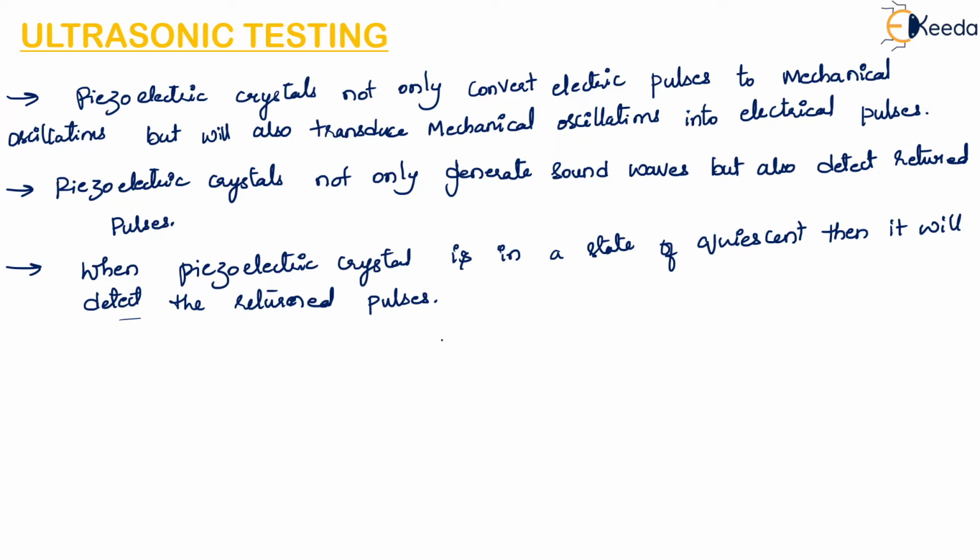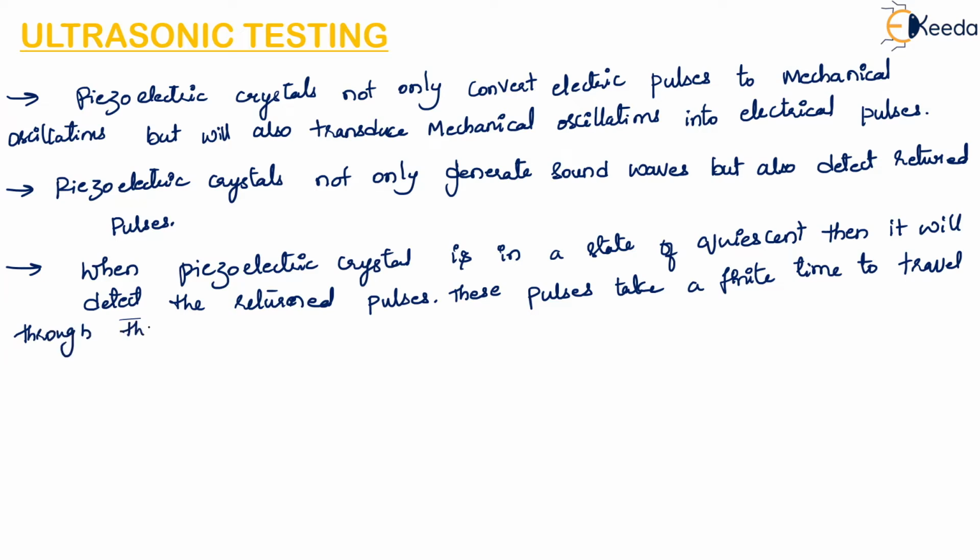These pulses will take some time to travel through the material to the interface and then be reflected back to the probe. So these pulses take a finite time to travel to the material interface and return back to the probe.